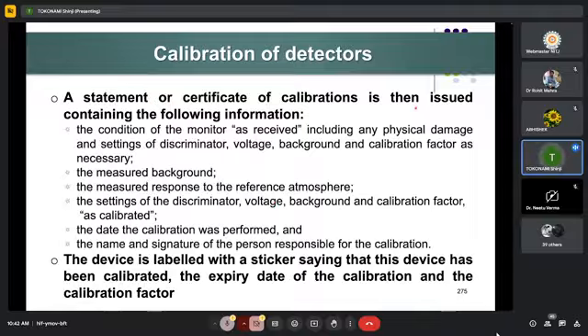A statement or certificate of calibration is then issued containing the following information: the condition of the monitor as received, including any physical damage and settings of discriminator, voltage, background, and calibration factor as necessary; the measured background, the measured response to the reference atmosphere, the settings of discriminator, voltage, background, and calibration factor as calibrated; the date the calibration was performed; and the name and signature of the person responsible for the calibration. The device is labeled with a sticker saying that this device has been calibrated, the expiry date of the calibration, and the calibration factor.